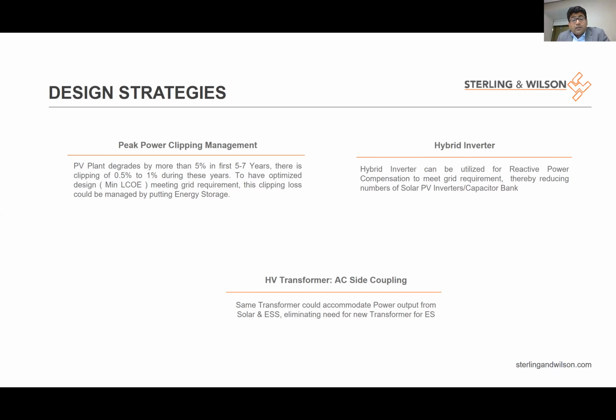Third strategy: rather than going for a separate transformer when you couple energy storage with solar, you can oversize the transformer which is being used for the existing solar power plant. The same transformer could be oversized, which is less costly, and used to inject power into the grid. So these are the typical strategies used to optimize the LCOE of the entire system.